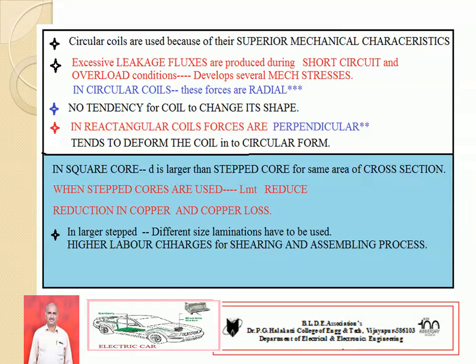In a square core, the diameter of the circumscribing circle D is larger than that of a stepped core of the same cross-sectional area. The area of the circumscribing circle is π D² / 4. In stepped type of cores, the length of mean turn (LMT) of winding reduces. As the LMT reduces, the requirement of copper reduces, and therefore copper loss also reduces, which increases the efficiency and performance of the transformer.